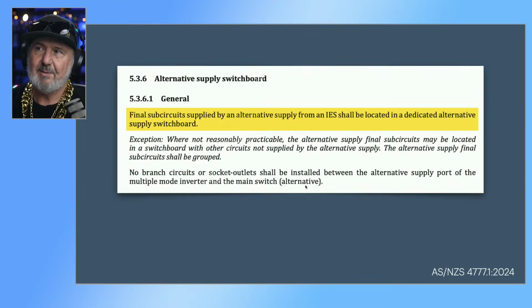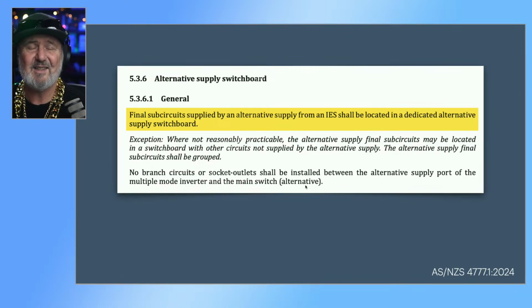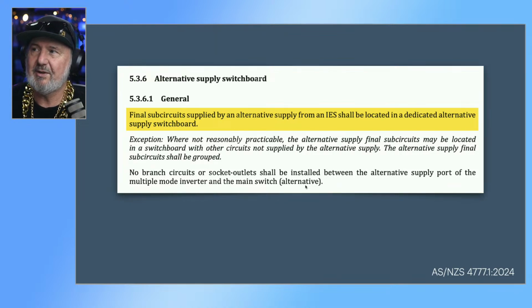So, final subcircuits supplied by alternative supply from an IES. IES, don't we love our TLAs, our three-letter acronyms? Inverter Energy System or systems is another way of referring to an inverter. It's a little bit more generic. So final sub-circuits supplied by an alternative supply from an IES shall be located in a dedicated alternative supply switchboard. So take a deep breath. Oh my gosh, I've got to put in a new switchboard every time I have a backup circuit.